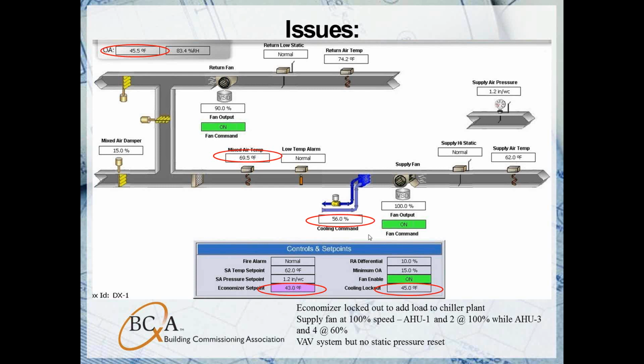Now some issues with the air handler, like we discussed earlier. What the facility staff is doing here is locking out the economizer mode. The outside air temp here is 45.5 degrees, and our economizer lockout set point is set below that, so we're not economizing. We're using mechanical cooling, which is operating fine for them. They're meeting their set point, but they are adding unnecessary load to their chiller plant, and they're doing it on purpose to keep those chillers operating.